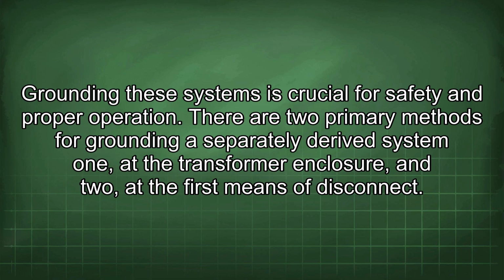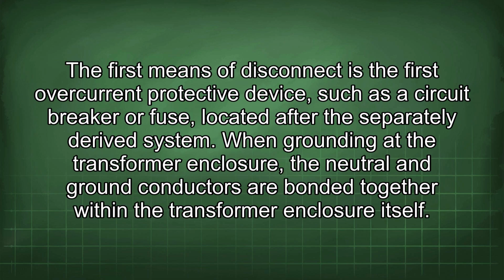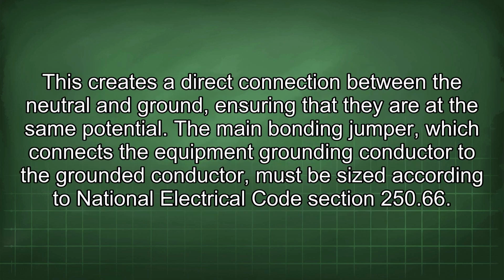There are two primary methods for grounding a separately derived system: 1) at the transformer enclosure, and 2) at the first means of disconnect. The first means of disconnect is the first overcurrent protective device, such as a circuit breaker or fuse, located after the separately derived system. When grounding at the transformer enclosure, the neutral and ground conductors are bonded together within the transformer enclosure itself. This creates a direct connection between the neutral and ground, ensuring that they are at the same potential.